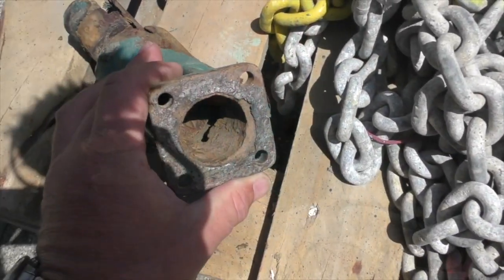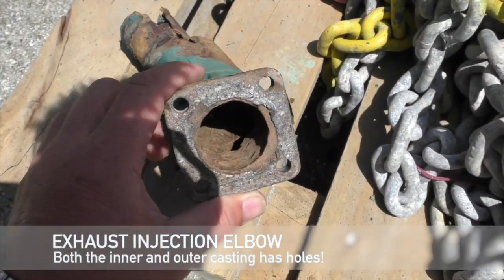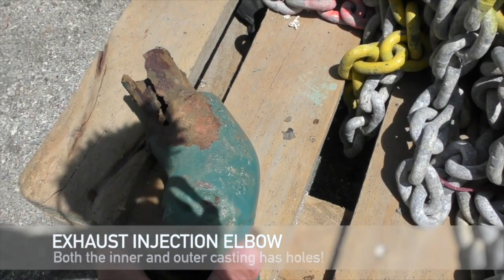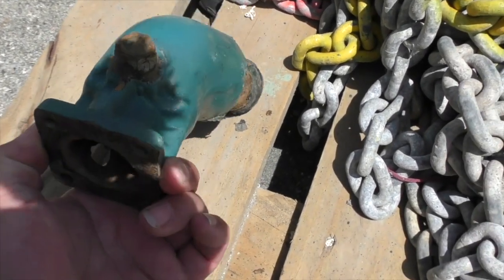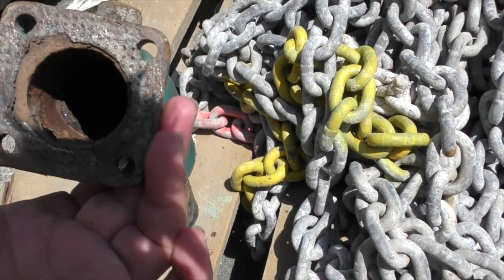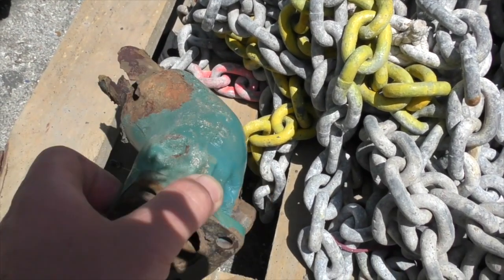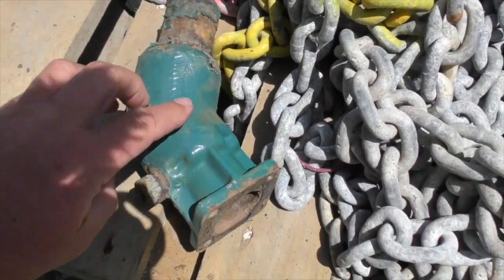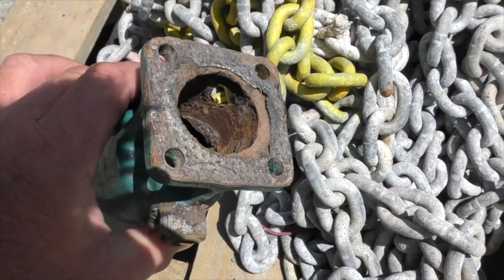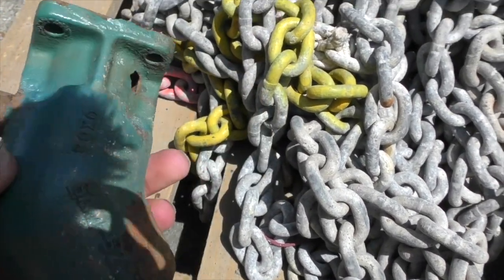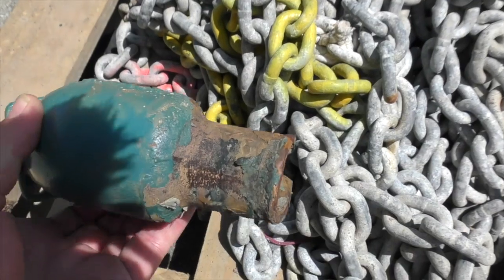It's important to say there was little or no indication that this exhaust injection elbow was in such a sorry state, or that it was leaking into the manifold heat exchanger. If you look at the actual holes, as soon as Pete started to clean it up, it disintegrated.